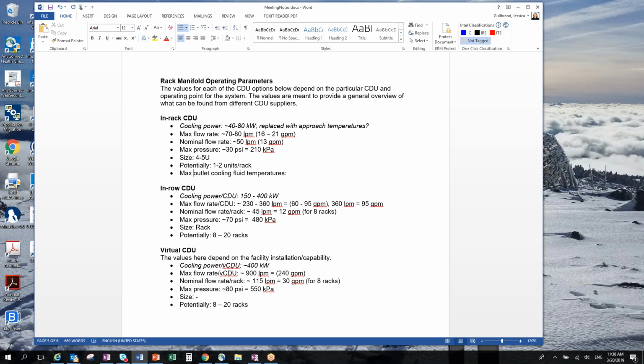I hear you as well, and we should definitely do that. But since there's no magic number, this is a bit of a struggle. There's no magic number for when you have to move to liquid cooling per se — it depends on your TCO model, when it makes sense for your particular installation to go to liquid cooling, when that becomes more cost effective. Since I can't put a specific kilowatt per rack figure that always applies, that's why I went down the CDU route.